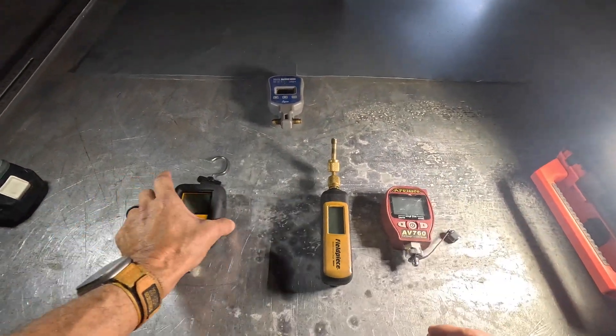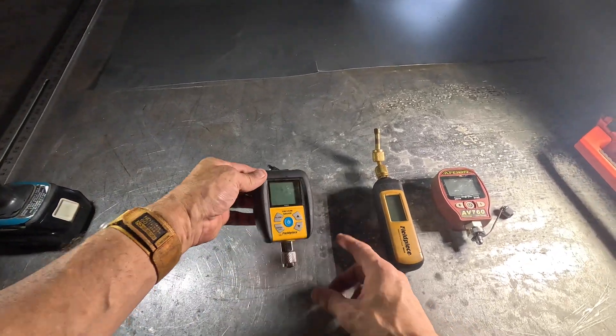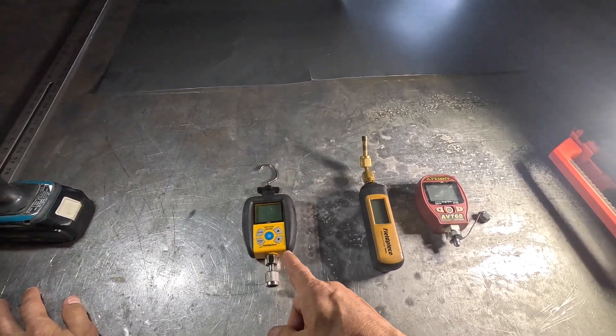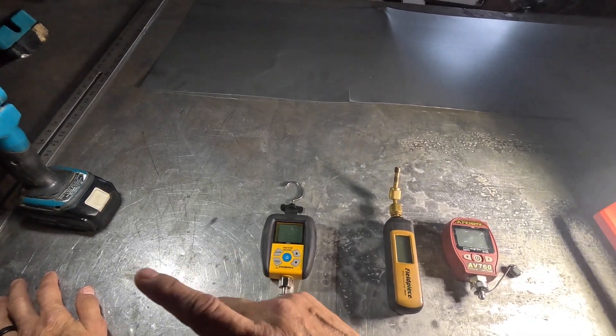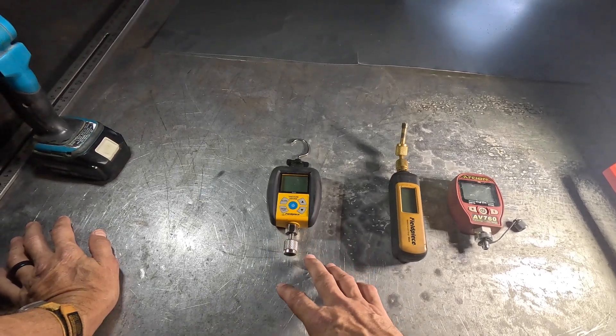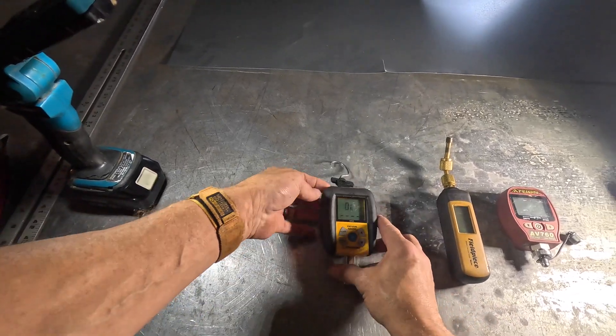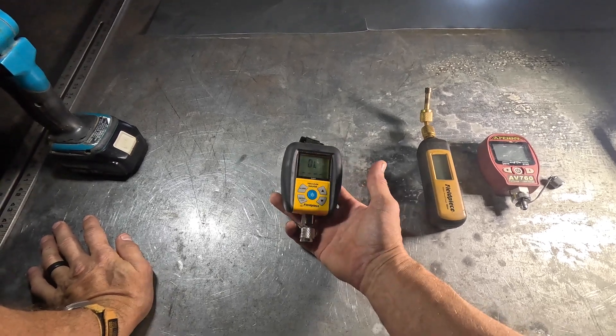The next one I started using was this Fieldpiece SVG3, and it has consistently been one of my better micron gauges. It just works, and as long as you keep it isolated from system pressure it will continue to work fine. I haven't had any problems with this — it just works.